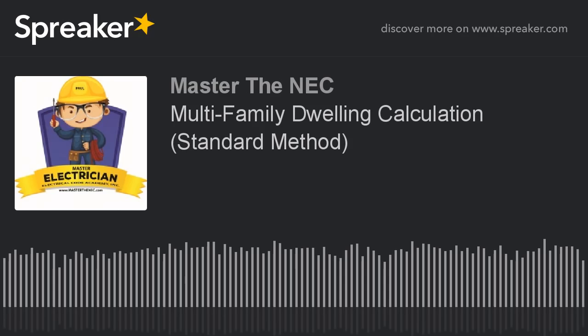Well, our dryer was 4.5 kW, but it says right here that we have to use 5,000 because it is larger than the 4.5. Now, if this was the optional method, we would just simply take the nameplate, and that's why the optional method can be a little simpler to do. But here we have to remember that we have to take 5,000 VA in our equation because that's what it says we have to do in 220.54.